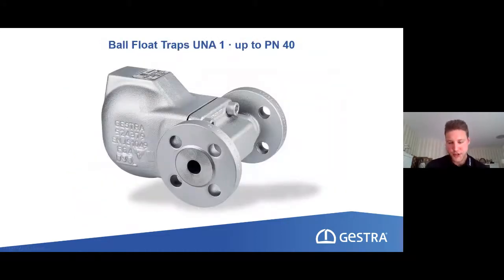Yeah, but as you can imagine, we have quite a lot of material with such a ball float steam trap, but it is always the most sophisticated and the best steam trap for each and every installation, because of its way of working. We don't have any banking up. The more condensate we get inside the steam trap, the more opening of the orifice we will get. So it is controlling in a way which makes it suitable for heat exchangers, for instance, but also for steam line drainage if we don't have that much space. But of course, because of the lot of material, compared to the other ones, it's not the cheapest solution.